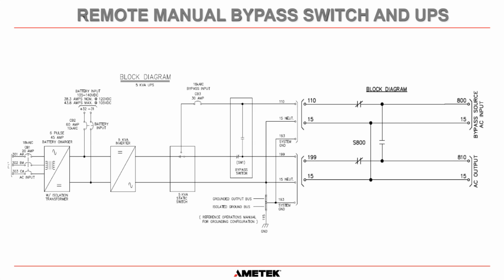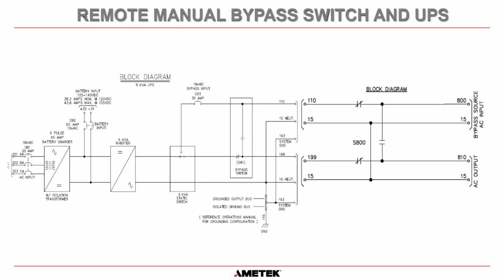And just for interest, this is how an external RMBS is connected with our UPS systems. This section here is an AMETEK SCI UPS. This section here is an AMETEK RMBS. So this is the RMBS. Excuse my handwriting with this pen, and this is the UPS. There are two individual pieces of equipment, but they are designed to be connected together. You can see here that terminal 110 connects to terminal 110 inside the UPS. The neutral is 15. Now this is from your MCC, and it's going to be 120 volts. This is your bypass supply.